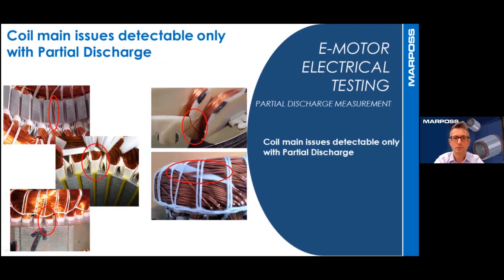In case of a stator wound with round wire, the main insulation issues between windings and stack, detectable only with partial discharge, could be a wire out of the slot that touches the stack, an insulation paper not completely inserted, or a piece of wire left inside the winding. And between windings, the main insulation issues could be partial short circuit between turns of the same winding, cross with the contact of wires from different windings, and short circuit between turns of different phases due to a phase insulator not properly positioned.